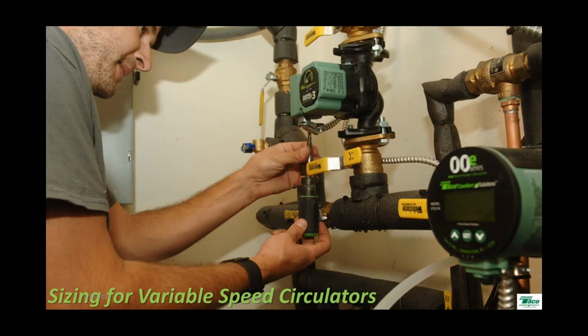So let's talk about sizing for variable speed circulators. A lot of people still think, well, they're variable speed, you stick it in and it figures it out for you. It sizes itself, it finds its own place. That's a great story, but fundamentally untrue across the board, every manufacturer, though it does make for a nice story. And I've heard high profile people in this business say, oh yeah, you're going to love it, it's magic, it does the thinking for you, it takes the thinking out of it. And none of that is true.